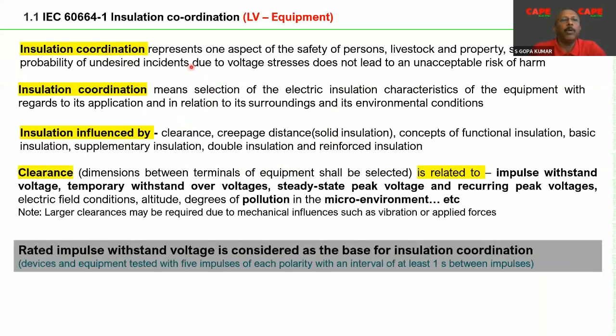Now, there are several parameters which influence the insulation level of our equipment, such as clearance, temporary over voltage, impulse withstand voltage, steady state peak voltage, recurring peak voltage, pollution, degree of pollution, microenvironment. So many parameters are influencing the insulation of the equipment, but out of these parameters, the one which is important is impulse withstand voltage. So the rated impulse withstand voltage is considered as the base for insulation coordination. What is this impulse withstand voltage?